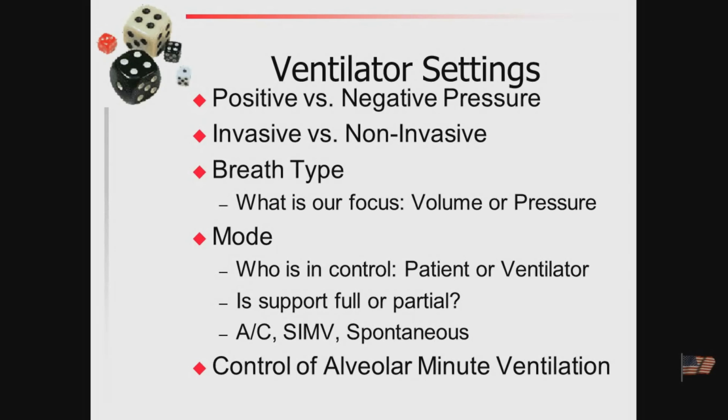Can you repeat the pressure method again? Sure. With a pressure-based breath, pressure remains constant. So changes in compliance and resistance will change the volume being delivered. As airway resistance goes up or lung compliance goes down, you're going to have less tidal volume delivered. Okay? So we want to be able to monitor the tidal volume to see when these effects are happening.